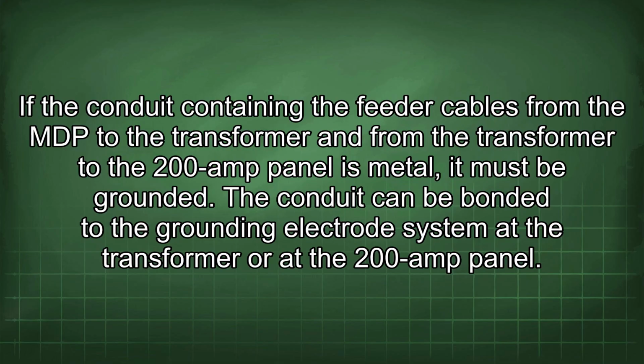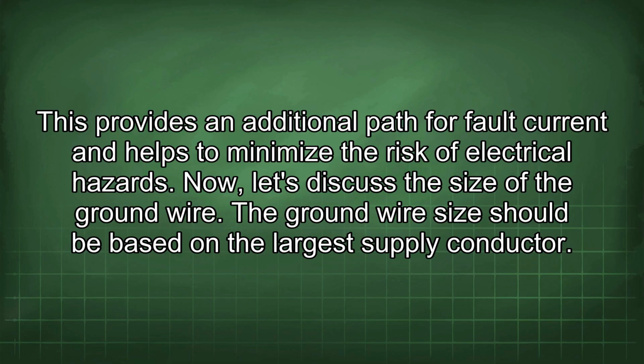If the conduit containing the feeder cables from the MDP to the transformer and from the transformer to the 200 amp panel is metal, it must be grounded. The conduit can be bonded to the grounding electrode system at the transformer or at the 200 amp panel. This provides an additional path for fault current and helps to minimize the risk of electrical hazards.